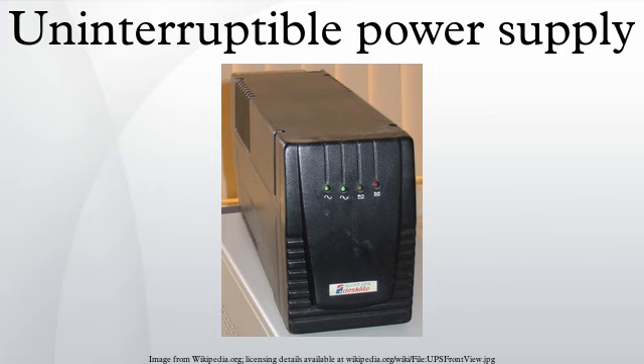DC has typically been the dominant power source for telecommunications, and AC has typically been the dominant source for computers and servers. There has been much experimentation with 48V DC power for computer servers, in the hope of reducing the likelihood of failure and the cost of equipment. However, to supply the same amount of power, the current would be higher than an equivalent 115V or 230V circuit. Greater current requires larger conductors, or more energy lost as heat. Most PCs can be powered with 325V DC. This is because most ATX switching power supplies convert the AC input voltage to approximately 325V DC.